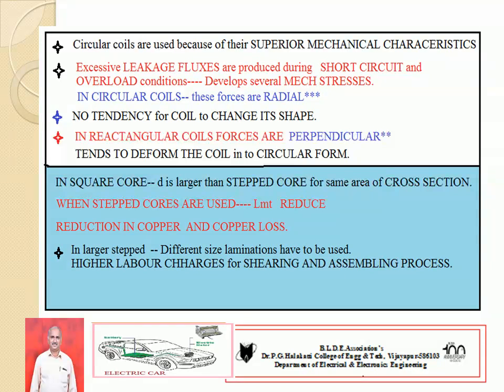If a larger number of steps are used, then different sizes of laminations are required. This creates a small disadvantage — an increase in labour and charges for assembling and shearing of these laminations. But this is not significantly considered. We have to consider the reduction of copper loss and the reduction of copper. Hence, in general, stepped cores are more useful for higher rating transformers.